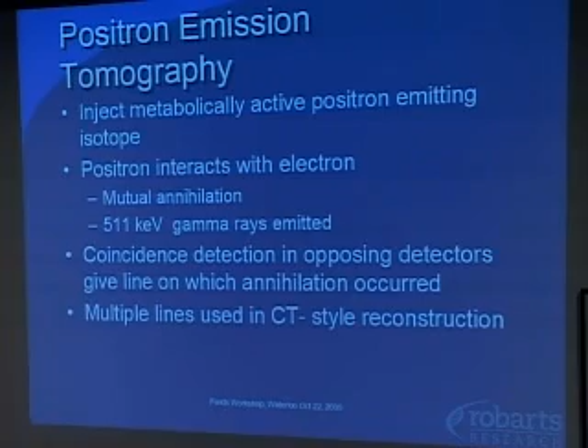Another technique that has actually been around for quite a while, and it's only been in the last, at least in Canada, 10 years where it's really started to be installed and be used. Positron emission tomography works by injecting a metabolically active positron-emitting isotope. Positrons meet electrons, they annihilate, generate 511 keV gamma rays. Set of detectors that record these. And once you've recorded that sort of data, you've got the data in the same form that we would have for a CT reconstruction.